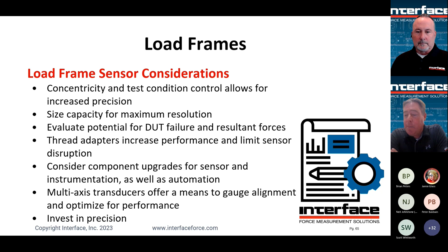Multi-axis transducers are a great way of gauging how well the frame is aligned. So maybe it's a new frame, maybe you did some work on the frame, but if you can measure multiple axes, the example I would use would be a load cell that measures in a primary axial direction, and then perhaps the moments about X and Y of that primary axis would help you essentially gauge how well those frame platens and your load string are aligned. A lot of times it's very hard to ascertain, but that is a means of doing that. And of course, the better aligned it is, the more investment you put into making sure all of that load string is aligned, load frame aligned, best sensors. You're investing in trying to get the precision as high as it can be. So optimizing that measurement.